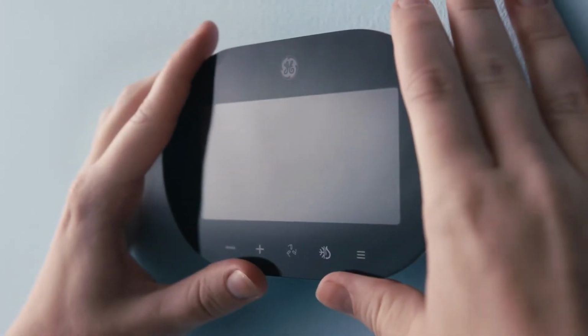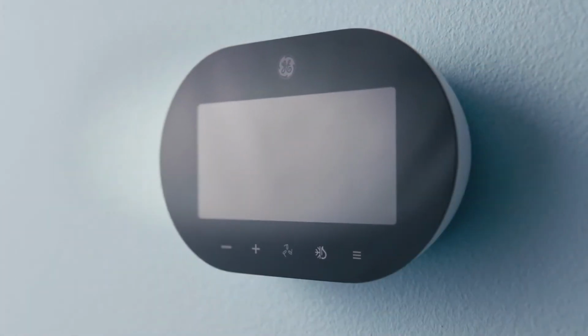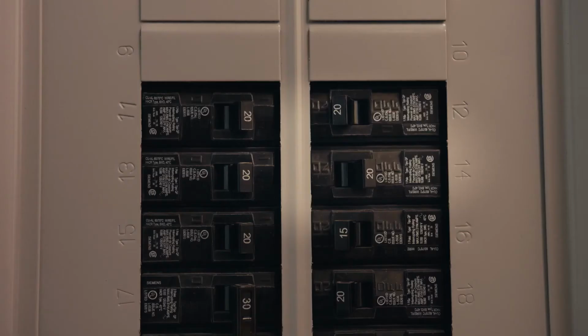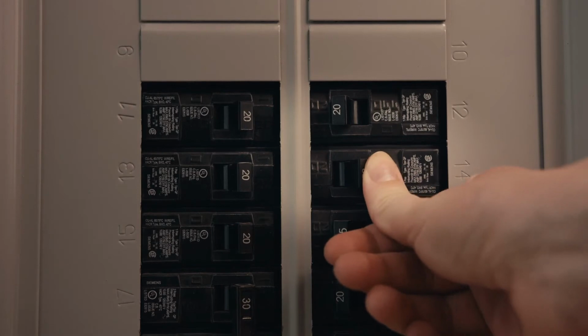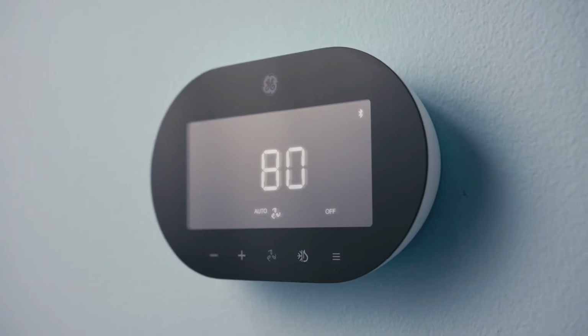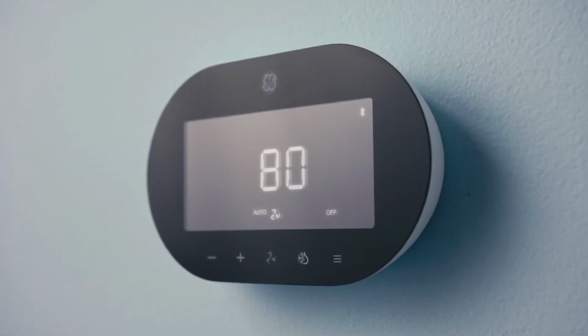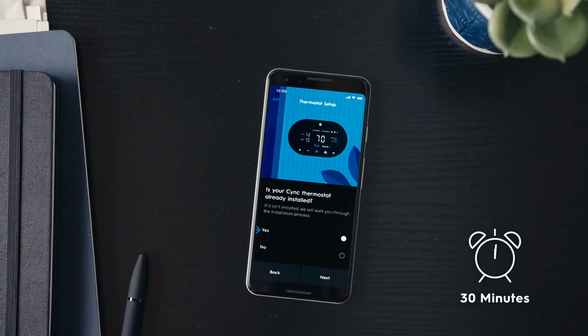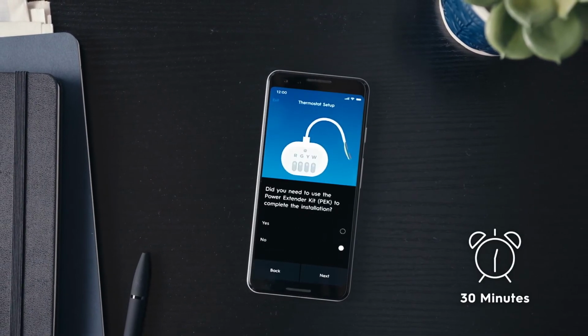Once aligned with the backplate, gently push the thermostat on either side of the screen until it clicks into place. Step 6. Restore power to your HVAC system to ensure everything is working correctly. If things are running smoothly, your thermostat should turn on automatically. Within 30 minutes of installation, begin setup in the Cync app.